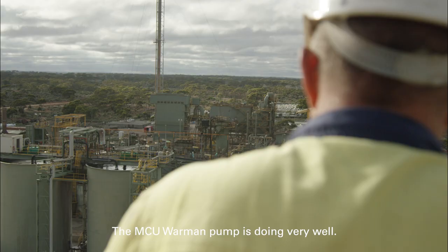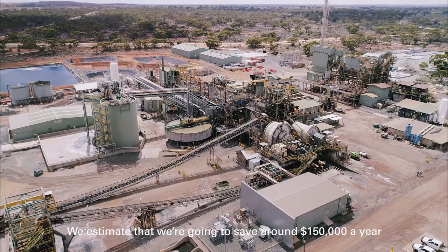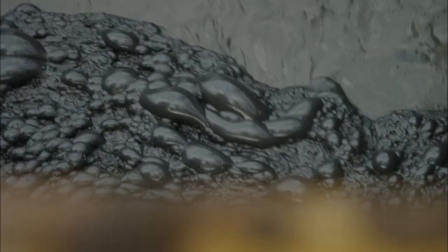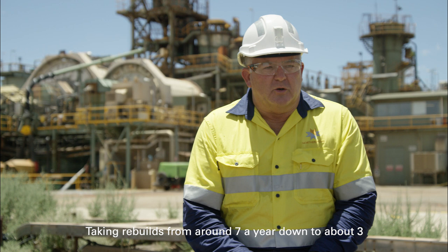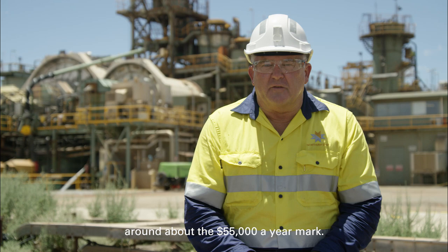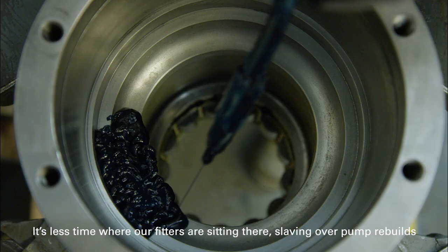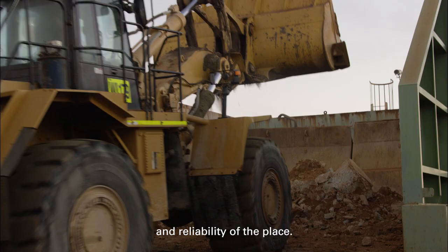The MCU Warman pump is doing very well. We estimate that we're going to save around $150,000 a year by having increased our run time between rebuilds from 1,000 hours to 3,000. Taking rebuilds from around about 7 rebuilds a year down to about 3, at around about the $55,000 a year mark. It's less time where our fitters are sitting there slaving over pump rebuilds, and now they're doing other stuff which is helping with the long-term improvement and reliability of the place.